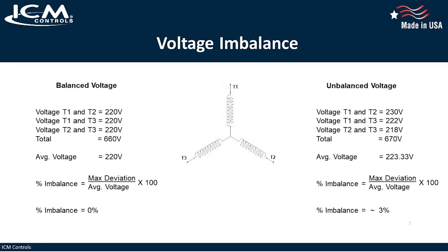Just find the maximum deviation from the average voltage and divide it by the average voltage itself, and multiply this number by 100 to get the percentage. Since voltage imbalance can occur anywhere in the electrical circuit to the component, you should check for imbalance at several connection points when trying to determine the root cause of the imbalance.